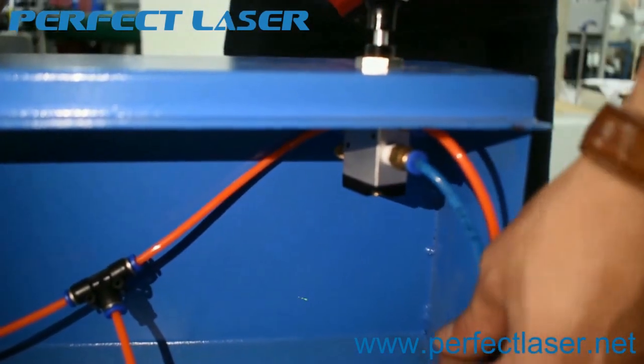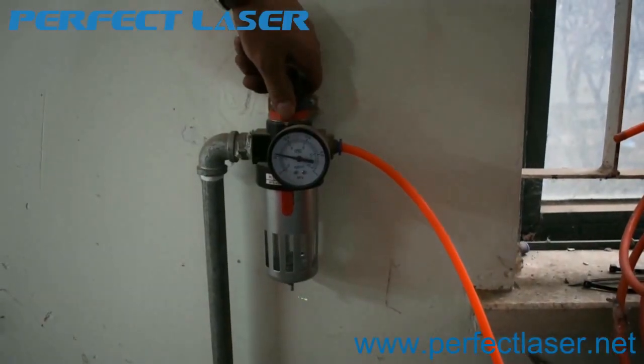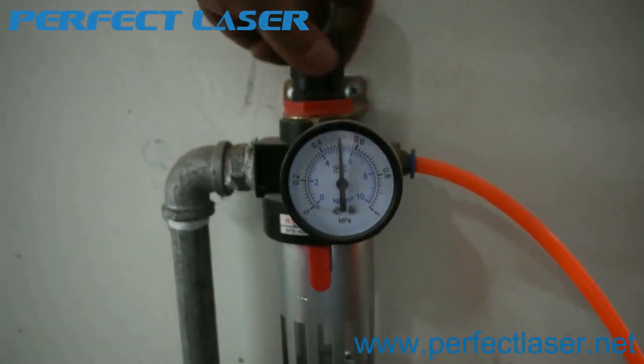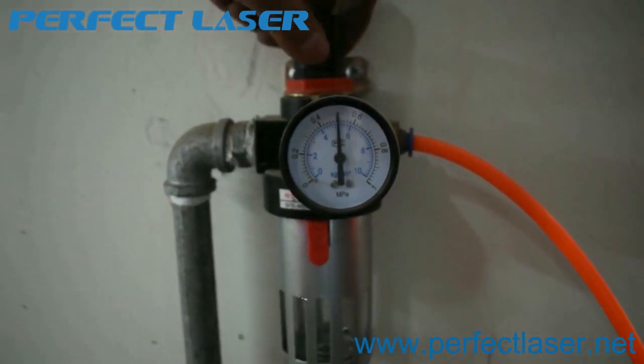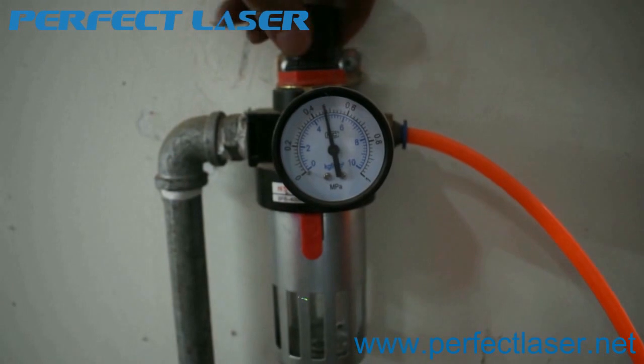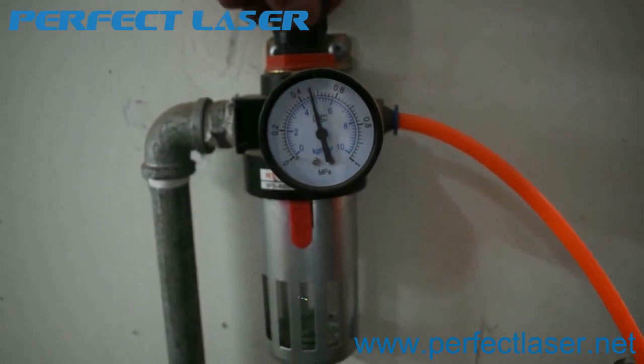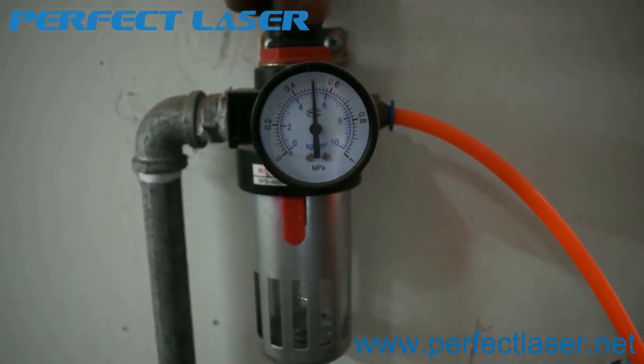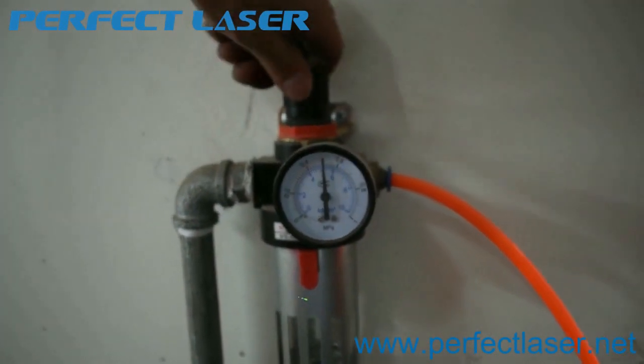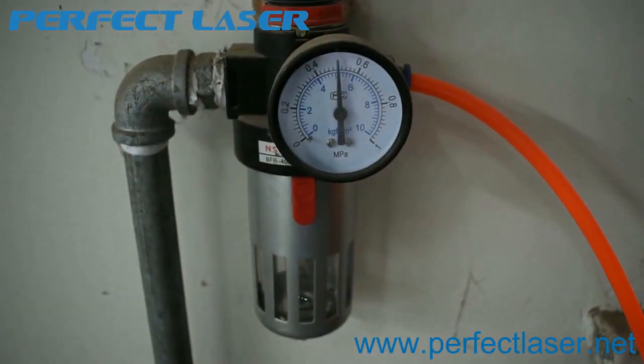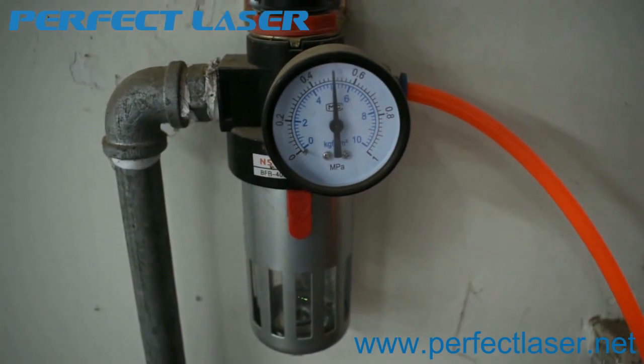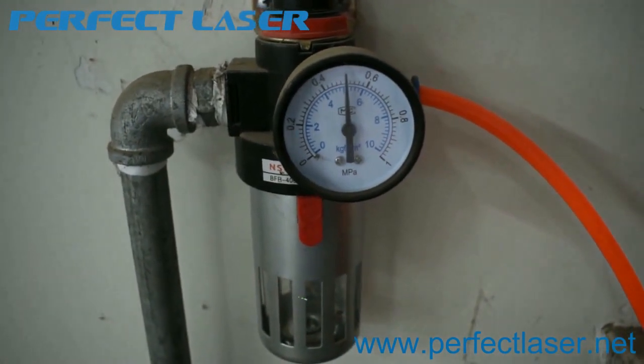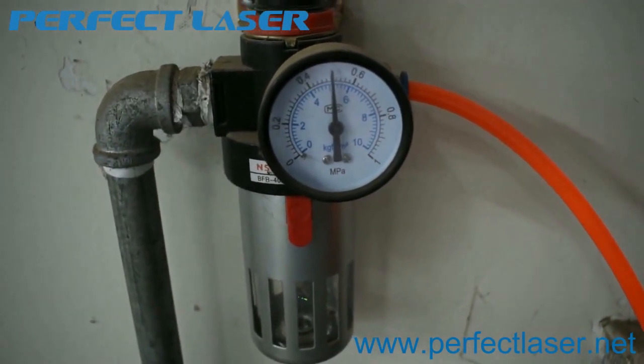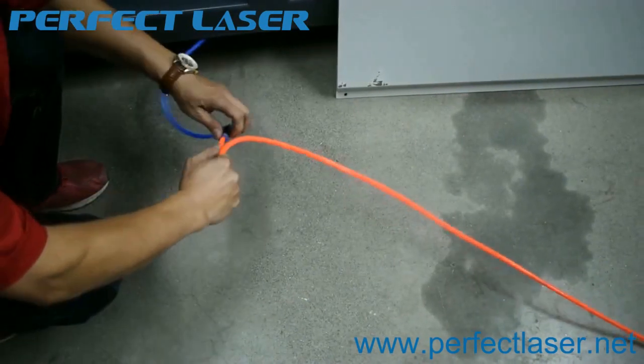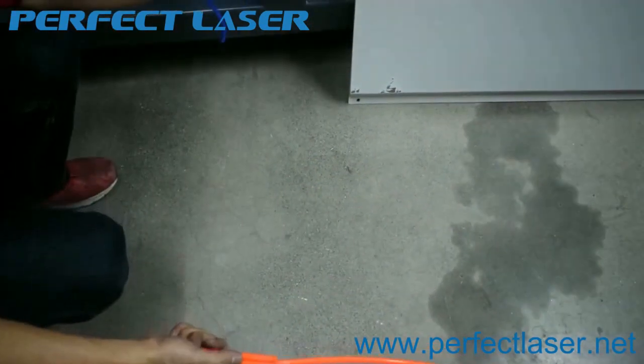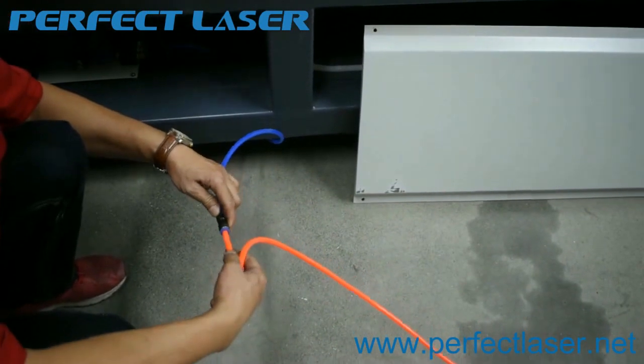Okay, here is the air compressor. Please set the pressure to 0.8. Because our air pressure meter has some problem, normally we need 0.8. The other side of the air pipe should be connected with the blue pipe.